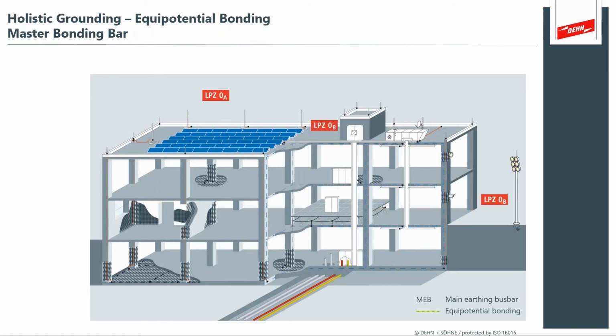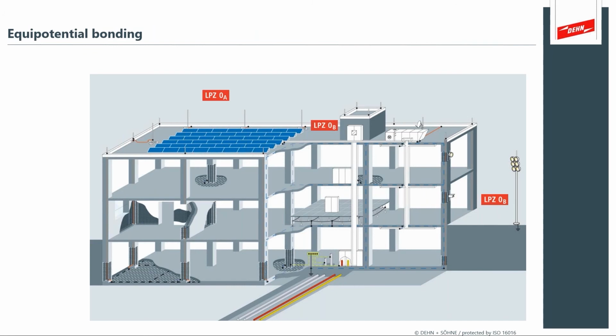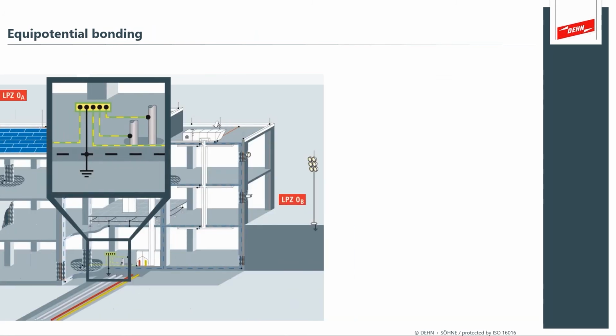So now we talk about the equipotential system with the master bonding bar that you'll see right at your electrical service entrance in a facility. The master electrical earth bar, it's essentially that first point of service entrance where the electrical service comes into the building, and the very first thing you do is you bond with your neutral ground bar. So this you see in some of our illustrations here is depicted as that master earth bar.